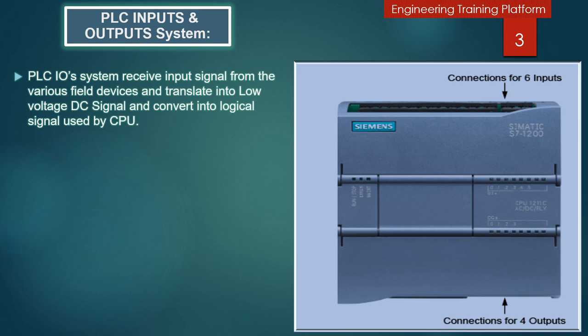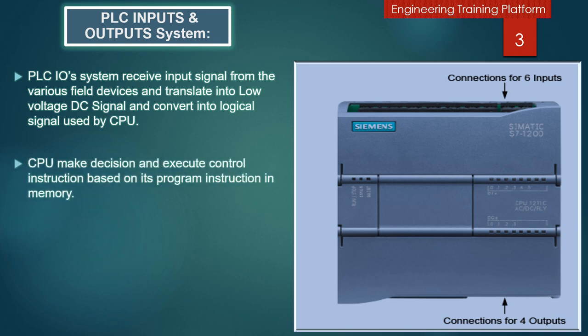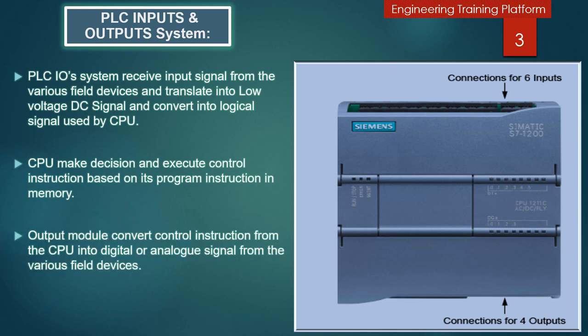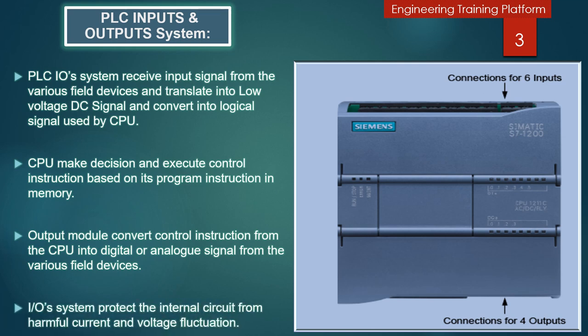The PLC I/O system receives input digital or analog signals from various field devices and converts them into logical signals used by the CPU with low voltage DC signal. The CPU makes decisions and executes control instructions based on its program in memory. The output module converts control instructions from the CPU into digital or analog signals for various field devices. The I/O system protects the internal circuit from harmful current and voltage fluctuations.